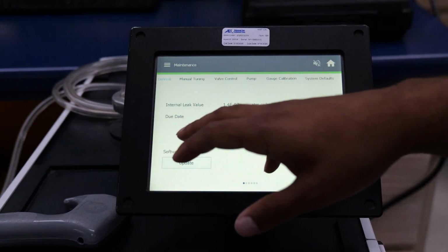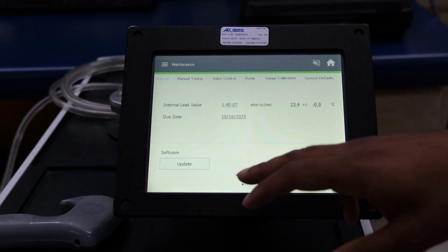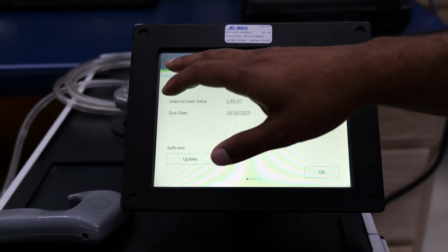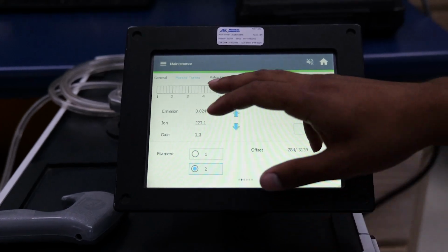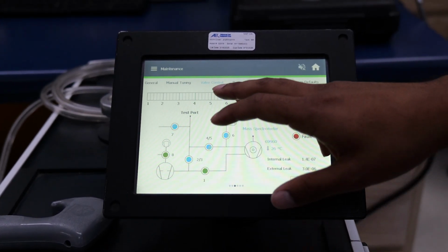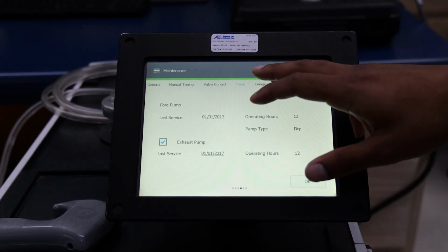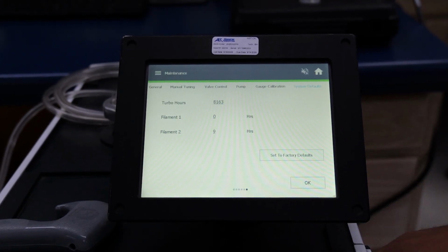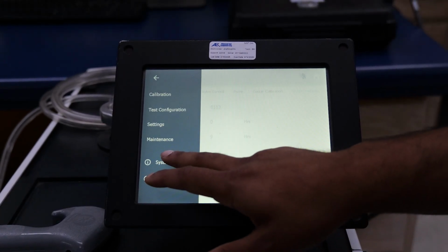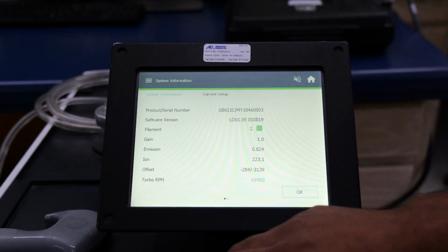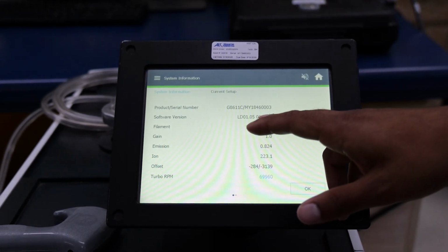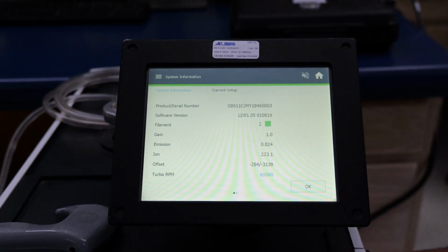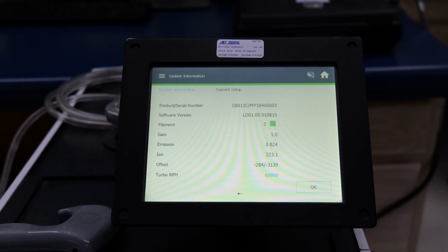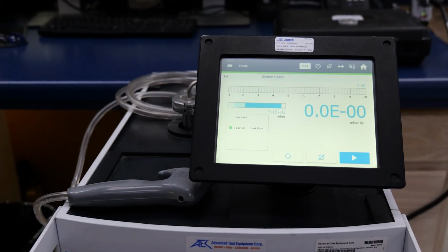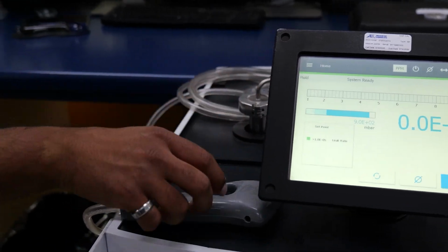In the maintenance tab, you can view the maintenance, the due date on the calibrated leak, and upgrade your software. There's additional manual tuning for all the different valves, different valve control, checking the pumps, gauge calibration, and you can always go back and set the factory defaults as well. Here you can view system information and see the filaments, software version, the serial number, and how fast that turbo pump is running.